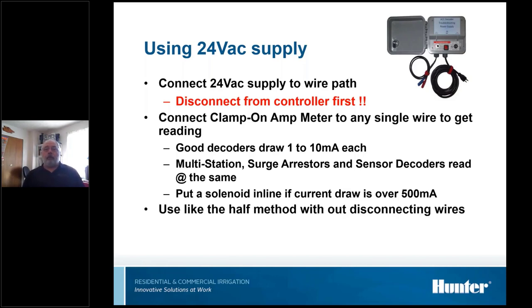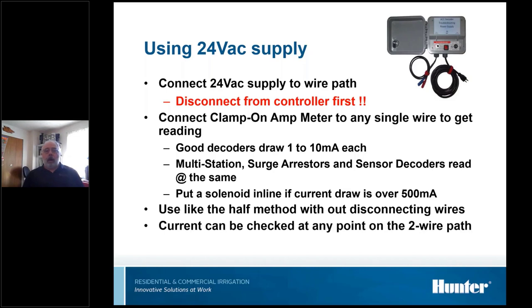If I see less than that, I don't put the solenoid in line, because it's easier to find the shorts if you don't have it there, because the readings are higher. Then it's like the half method, only we don't have to disconnect anything. So we're going to hook it up and get a reading. Same thing, I usually go to the first valve box and get a reading there just as a reality check before I go any further.